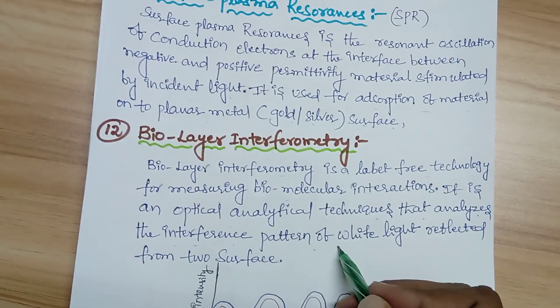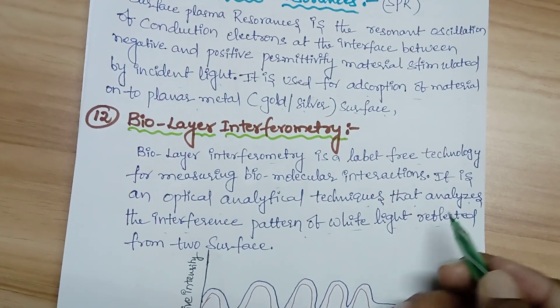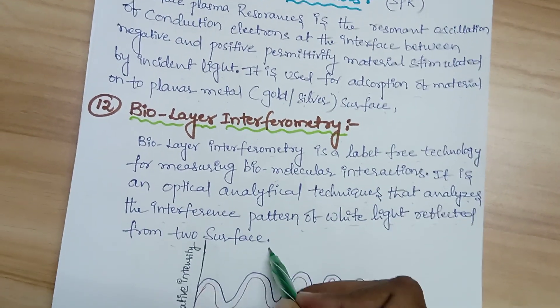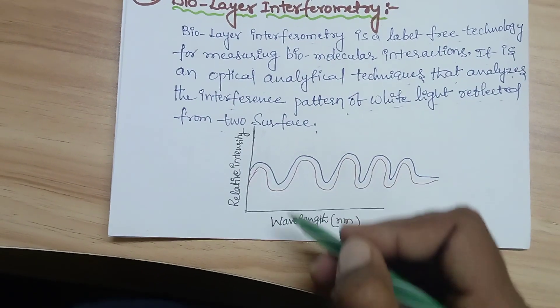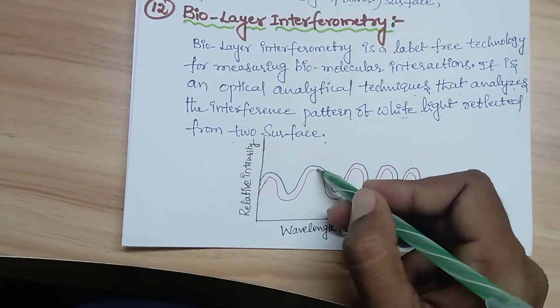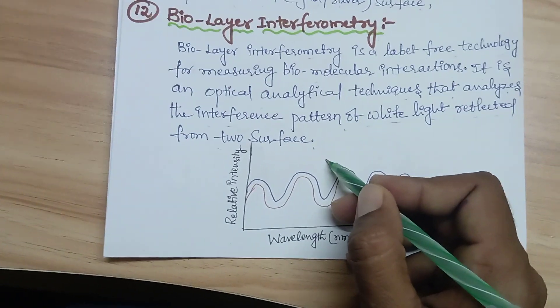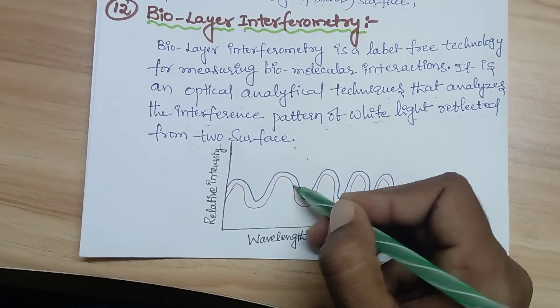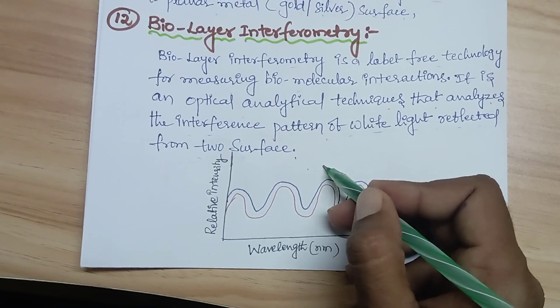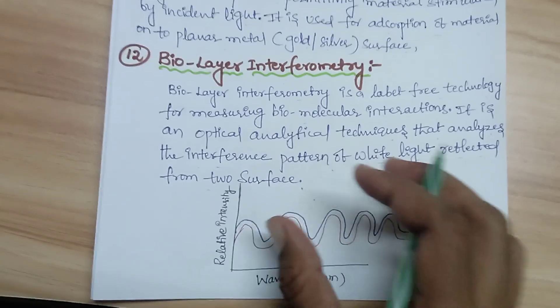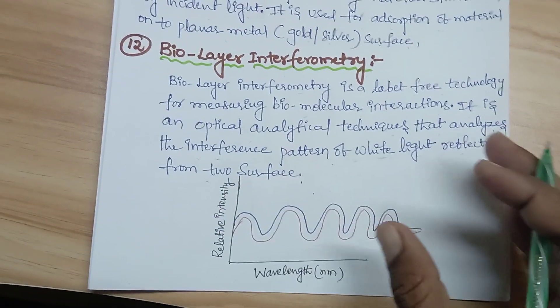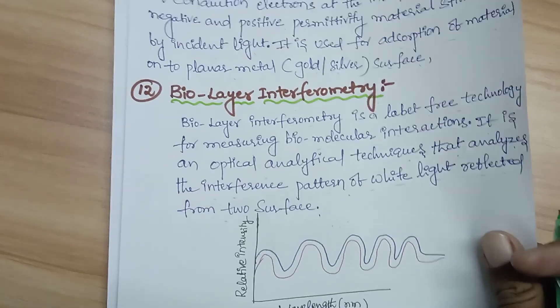I draw it here — a graph of relative intensity versus wavelength. The blue line indicates one surface of the layer and the red indicates the other surface. With BLI techniques, you can reflect from two surface layers simultaneously — that is the main benefit of biolayer interferometry.